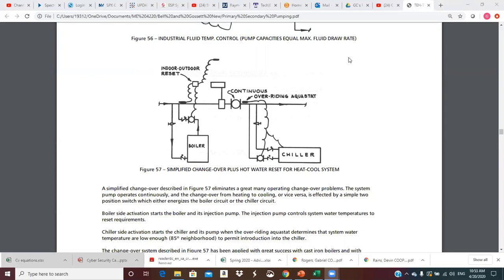When it's cold outside we'll have hotter water circulating. When it's not quite so cold — maybe 35 to 40 degrees — and we still need some heat, we don't need our highest water temperature. Chiller side activation starts the chiller and its pump when the overriding aquastat determines that system water temperature is low enough — somewhere around 85 degrees — to permit introduction into the chiller. You have to be careful: if we've been running the boiler, that water temperature may be too hot for the chiller. Around 85 would be the maximum; ideally closer to 70.